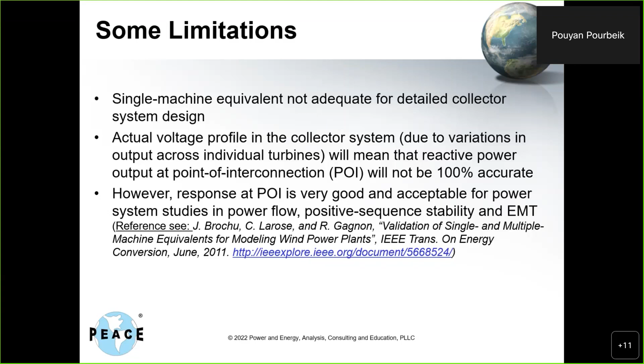I've given a reference from back in 2011, where Hydro-Quebec did a detailed, supercomputer-based comparison of modeling every single component in the plant in EMT, broken down to gory detail, then 5-machine aggregate, 3-machine, 2-machine, 1-machine, and showed that the POI electrical response was almost exactly the same. So if we're interested in looking at it from the POI, how the plant is interacting with us, the aggregate is adequate.